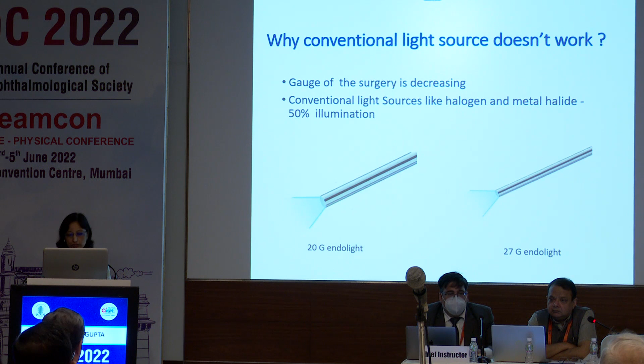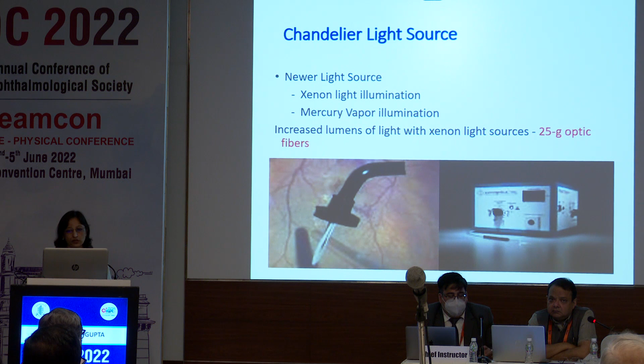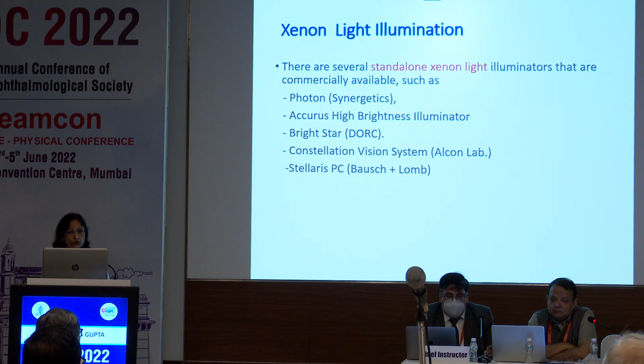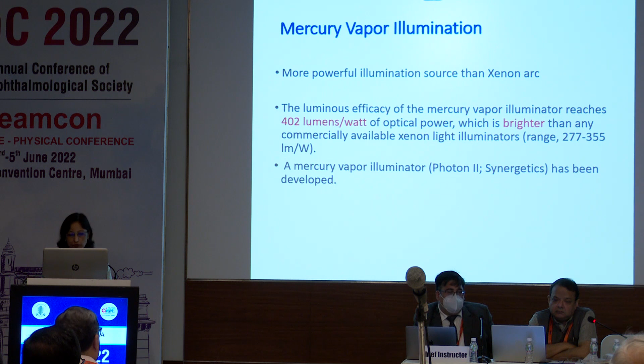To compensate for this decrease in brightness, newer light sources were introduced, like xenon and mercury, and the kind of illumination we achieve with xenon and mercury sources is equivalent or better than the conventional light sources. So there are various standalone xenon light illuminators that are commercially available, like Photon, Accurus, Brightstar, Constellation Vision Systems, Stellaris PC. And mercury vapor illuminators are a much better and brighter source of illumination, with luminous efficacy reaching up to 402 lumens per watt, which is brighter than any commercially available xenon light illuminator.